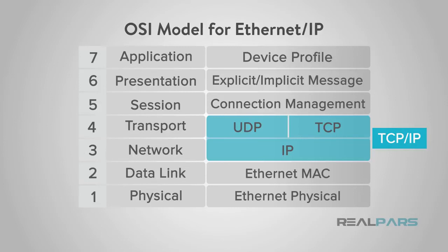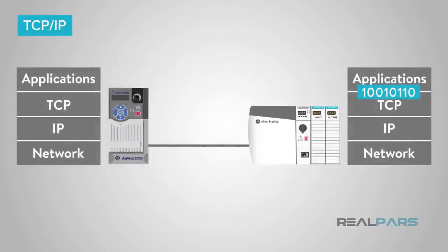We need to break down the TCP/IP, or UDP protocols slightly to give you an idea of which application may use which type. In the TCP/IP protocol, there's somewhat of a send-receive-acknowledge relationship. The packets go down the stack, received at the device connected to your network. A receipt confirmation goes back up the stack to the applications layer. This type of protocol may be used with a VFD where you command a speed and need to ensure that the VFD received the message.